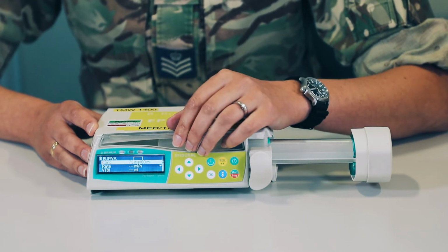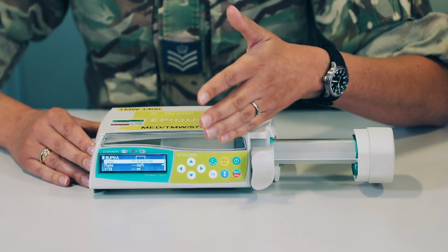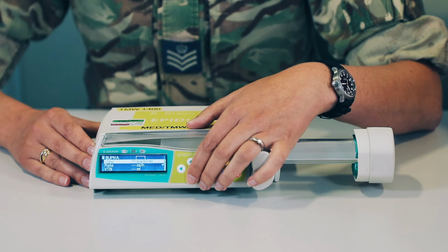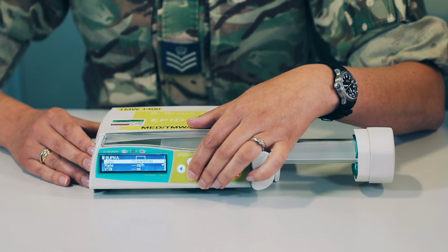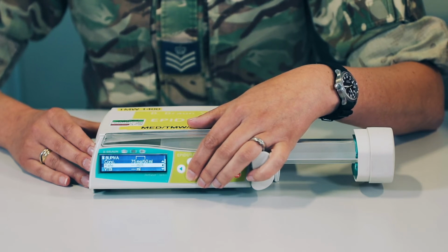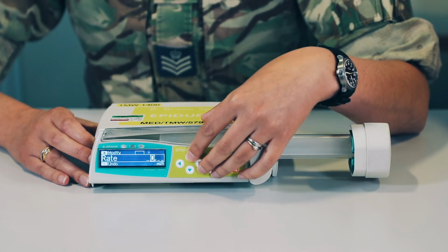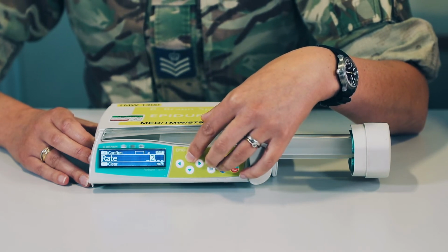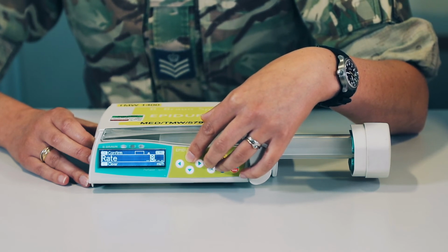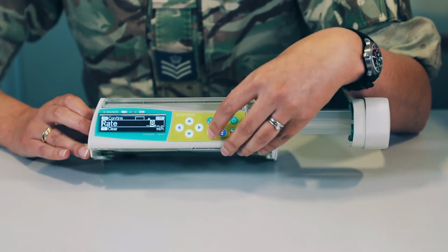Press the arrow facing in towards the screen again and it now takes you through to the setup menu. From here you can see that it's slightly different to the perfuser because we've selected a drug. This first part here is reminding you of the concentration of that medication. Next we have our rate.